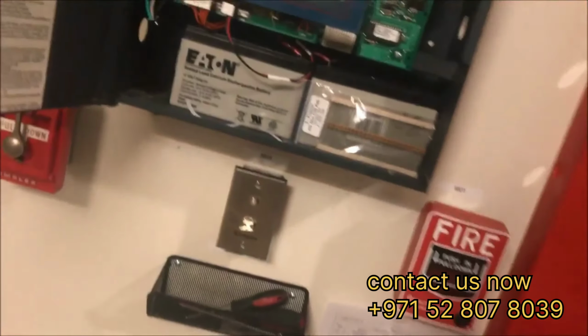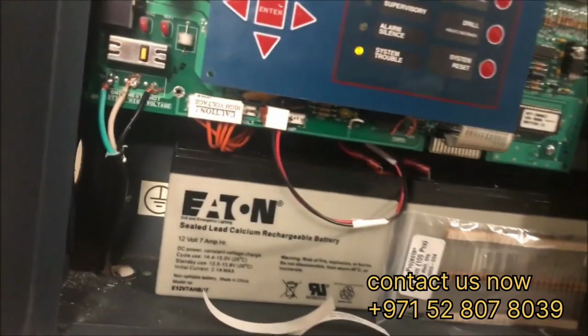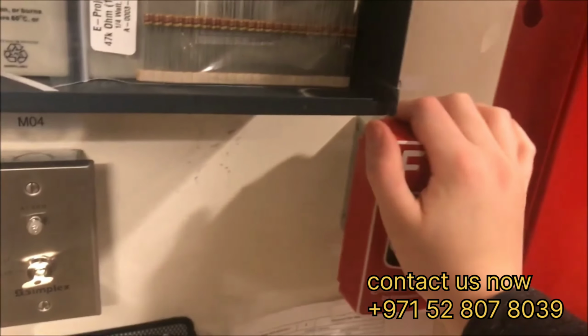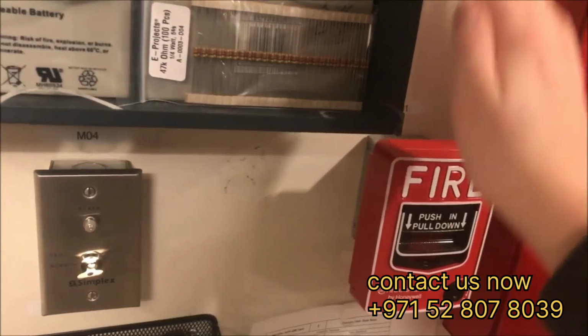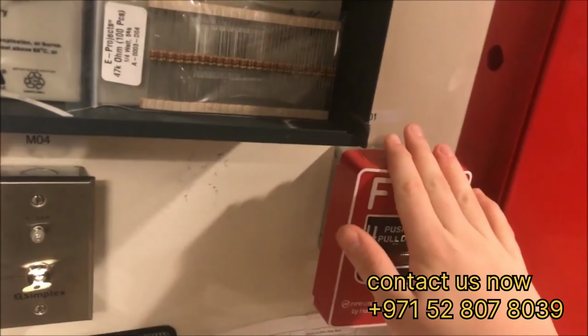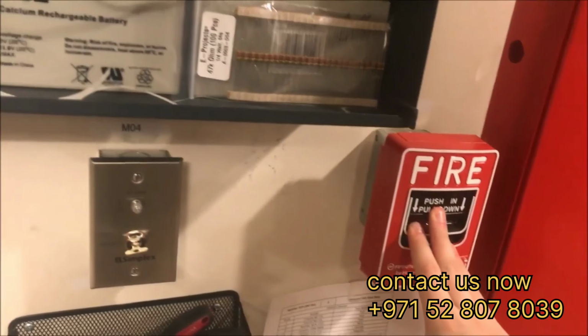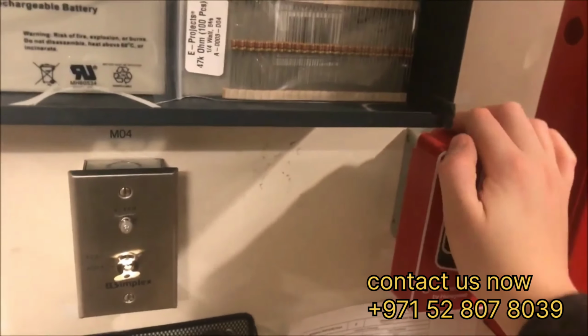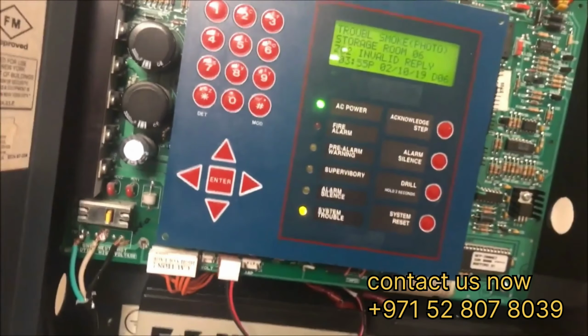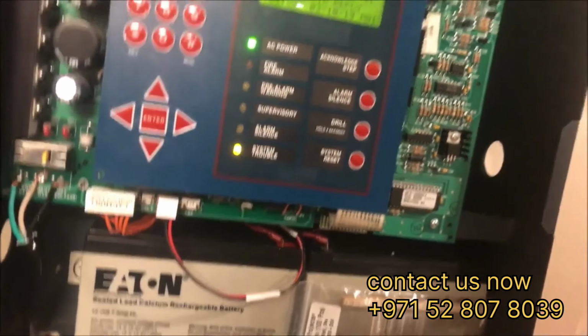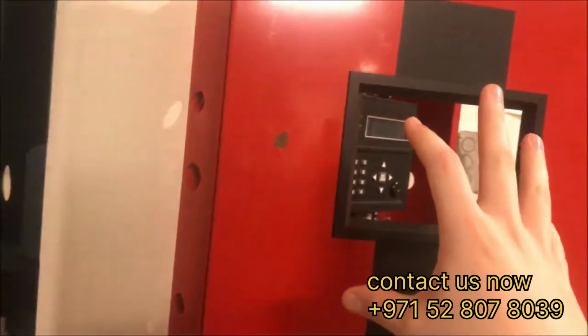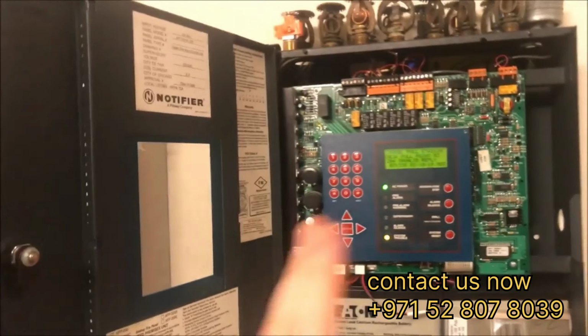If I want to disable this pull station, I can make it to only disable 0.1, meaning the pull station that could be right next to it works, but this one would not. I would have turned it off. So you can very selectively talk to each pull station. That's really the huge difference. You can selectively talk, or generally talk.